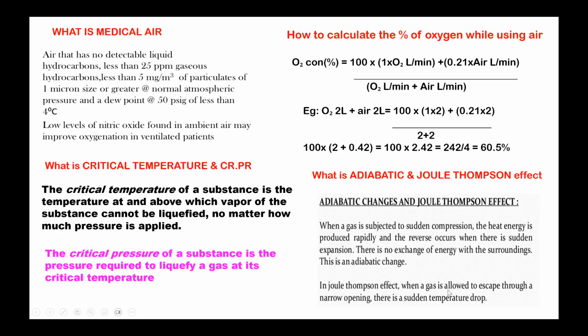In the Joule-Thomson effect, when a gas is allowed to escape through a narrow opening, there is a sudden temperature drop. How is it seen, and in which cylinder will you see this Joule-Thomson effect? You will see it with nitrous oxide, where droplets of ice form, because atmospheric air contains water vapor, and there is sudden cooling by releasing this nitrous oxide. That water vapor gets condensed and forms small ice particles around the neck and shoulder portion of the nitrous oxide cylinder, and that is called the Joule-Thomson effect.